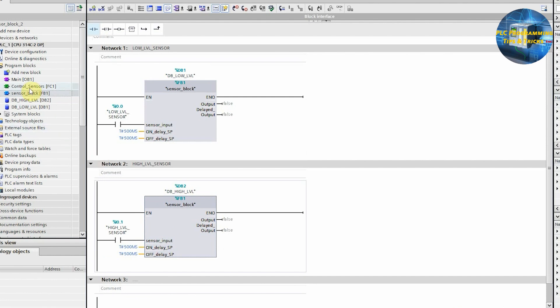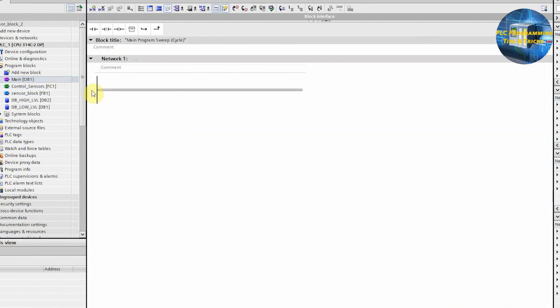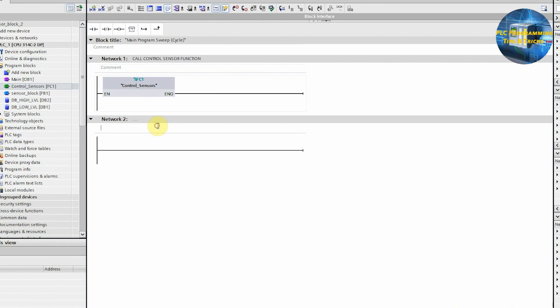One thing to note here is that we have done all this in function FC1. Now we have to call FC1 in OB1 so that this function gets executed. We will open the main OB1 block. In network number one, we will drag and drop the control sensor function FC1 onto the ladder logic. This way the control sensor function FC1 will be executed when the PLC goes into run mode.